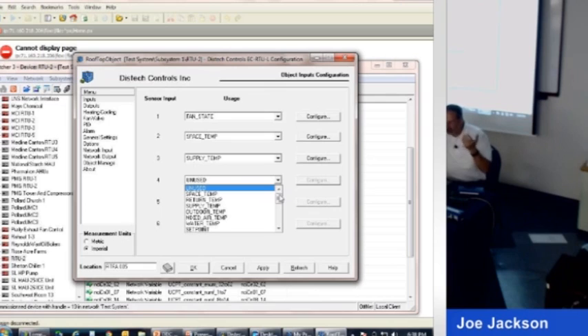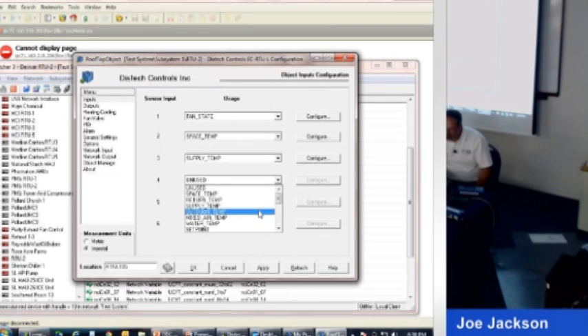Maybe you want the return temperature so you could quickly tell what the delta T is across the rooftop to see how well it's running. Supply temp we already got. Maybe you want the outside air temperature. Maybe, maybe not. Rooftop units, we typically wouldn't have a mixed air temperature sensor like this guy. But this same controller will also do a nice job for a simple air handler. If it was an air handler with hot and cold water, maybe you want a water temperature sensor. Not typical for a rooftop though, but maybe space humidity.